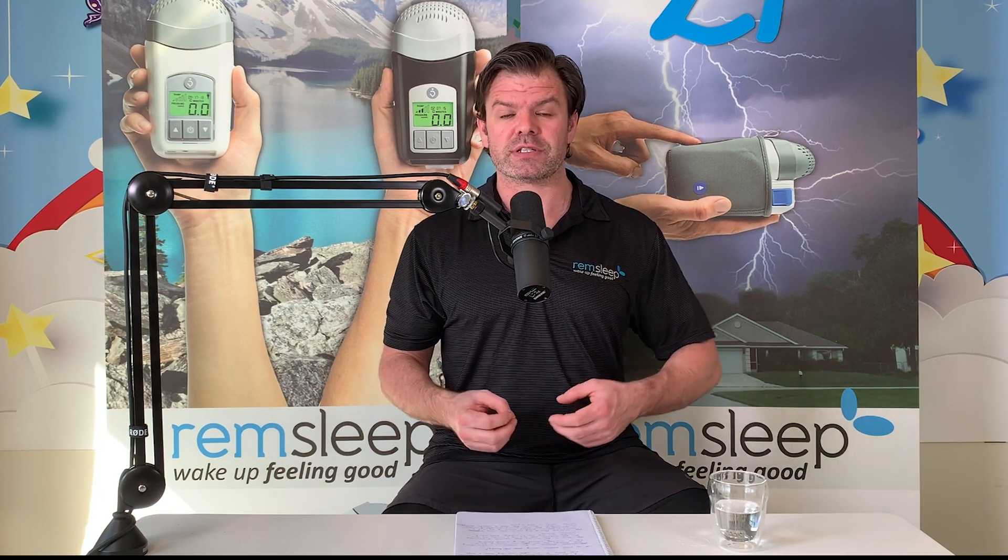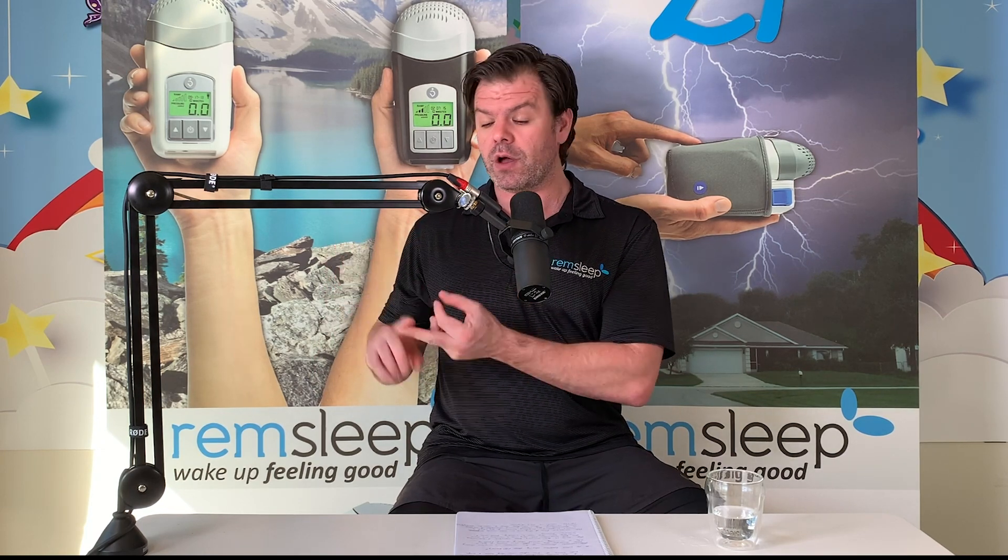One issue you're probably going to run into at some stage is a little dilemma called rainout — when that warm, humidified air starts condensating and turning into water droplets, which can gather in your tube and start gurgling, even spitting on your face. It's a really annoying aspect of CPAP therapy. Remember, cold air can't hold a lot of moisture, so when air gets cold it gets rid of its moisture content, condensates, and we get those water droplets. To fix it, we can either increase the air temperature so the air can hold more moisture, or reduce the level of moisture by decreasing the humidification settings. It's a bit of a balancing act.